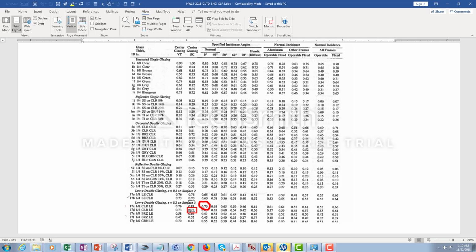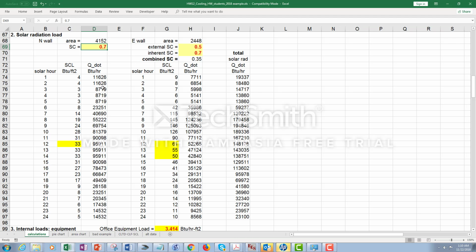It only loses transmittance because of reflection at the two interfaces. Take that 0.92, multiply it by 0.75, and you get about 0.70. So you see that this shading coefficient accounts for the extra attenuation compared with the nominal.